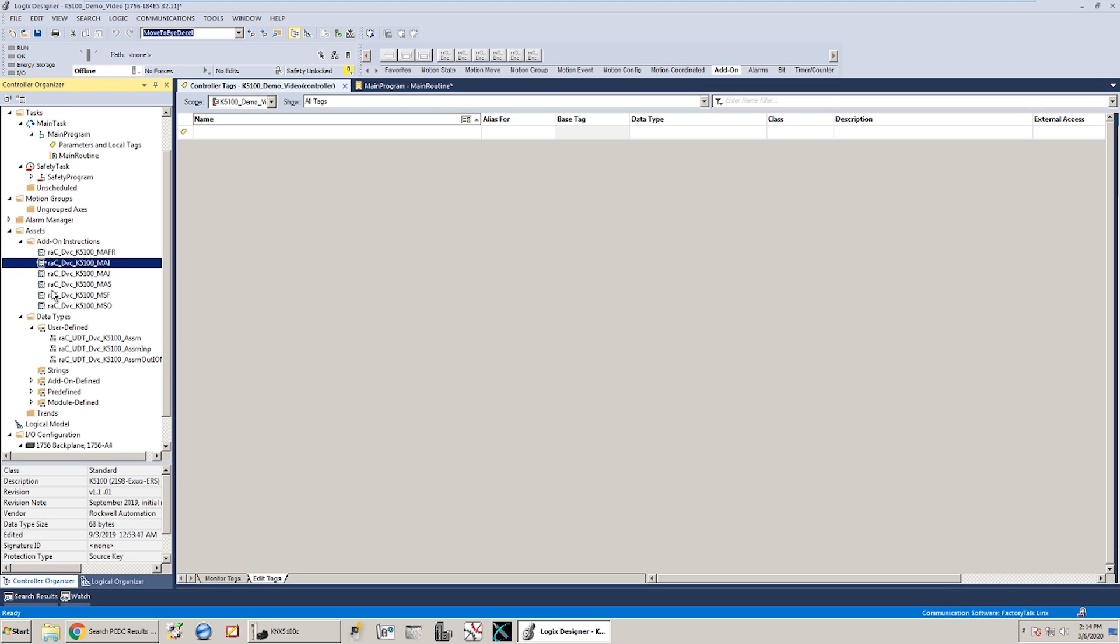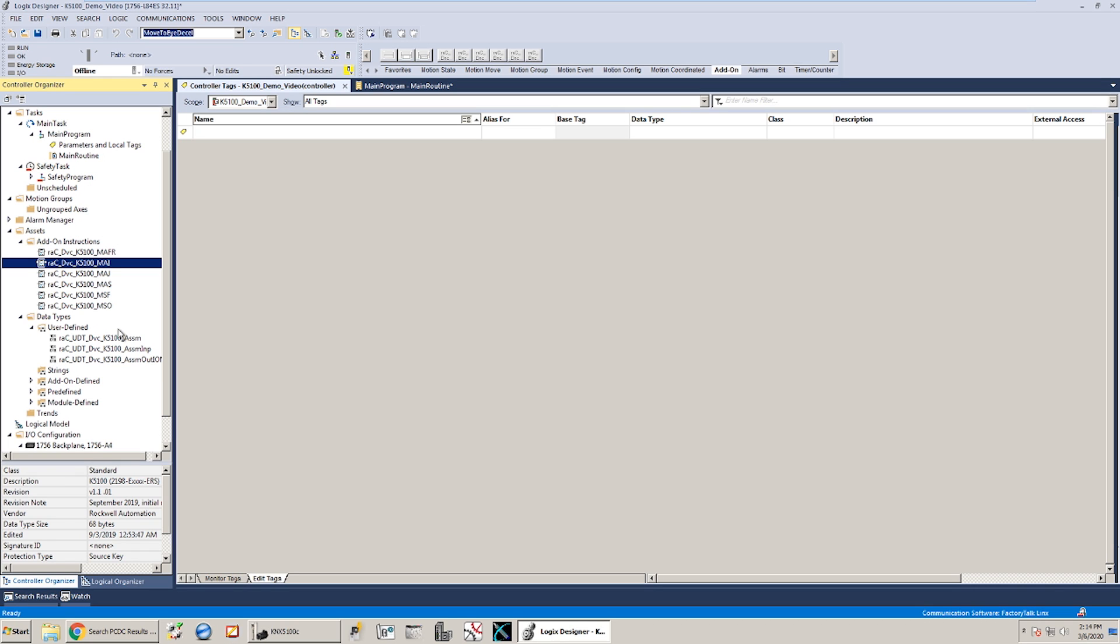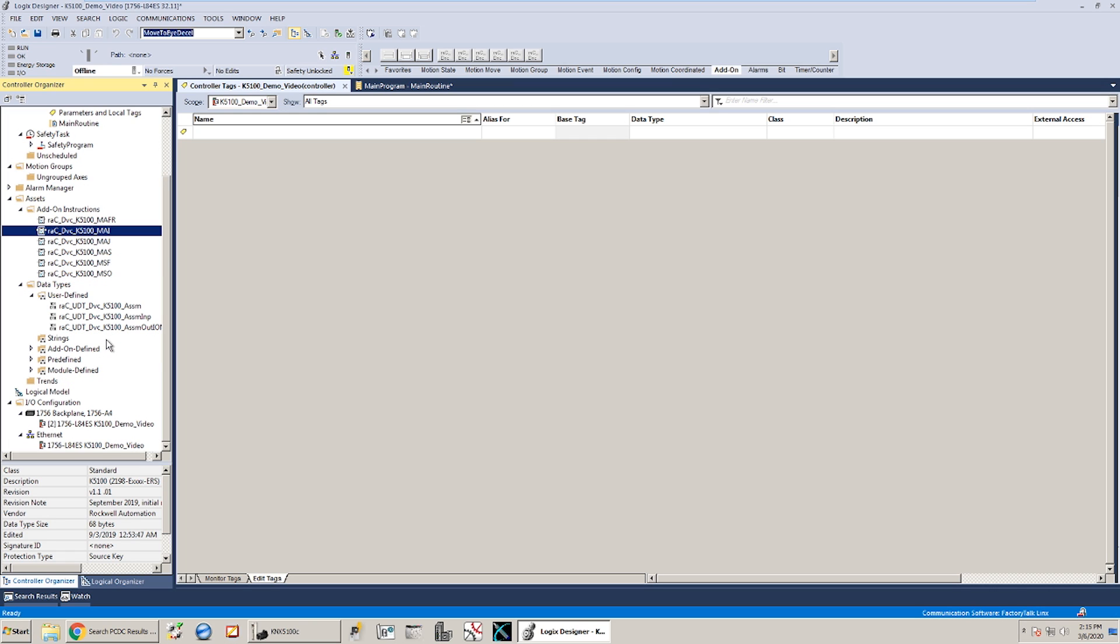Now you can bring them all in, you can bring in just the ones that you're going to need as far as the instructions go. For the data types you do need to bring in the three data types: there's an input assembly, an output assembly, and then an overarching assembly that's basically made up of those two parts. If you're familiar with doing integrated motion you can kind of think of this as your axis when we create a tag of this assembly type, and then that axis is going to link to the drive that we need to add in down on our Ethernet network.